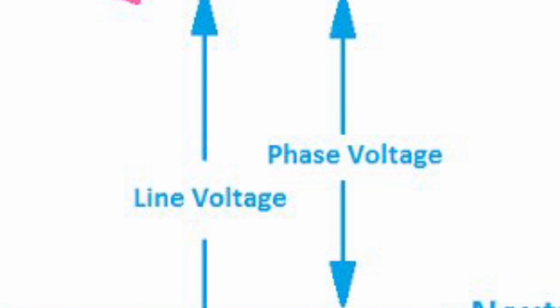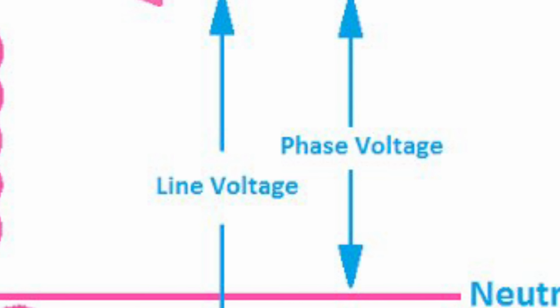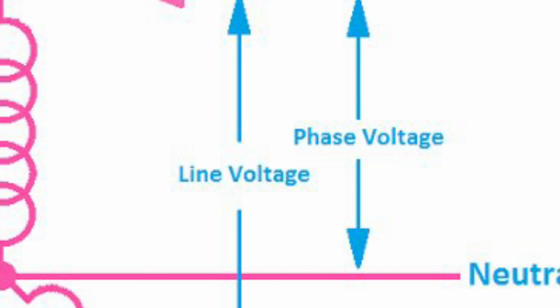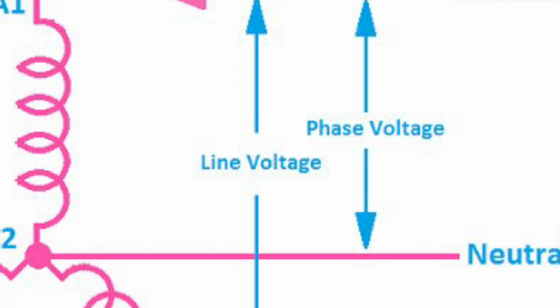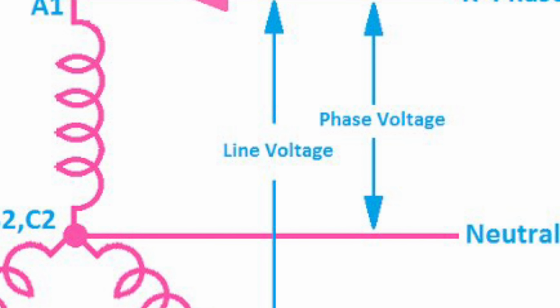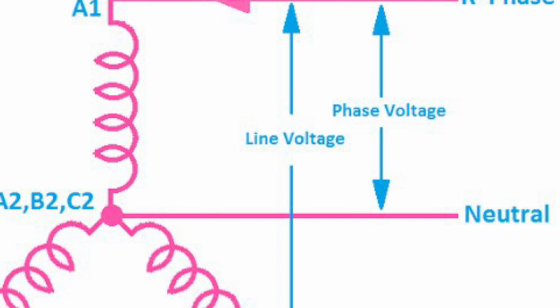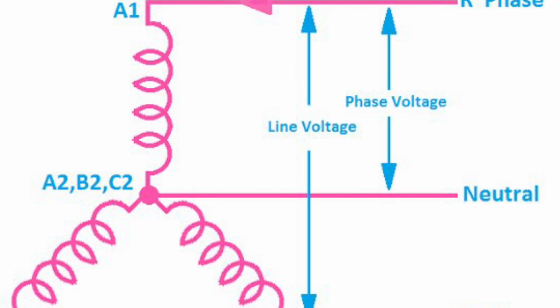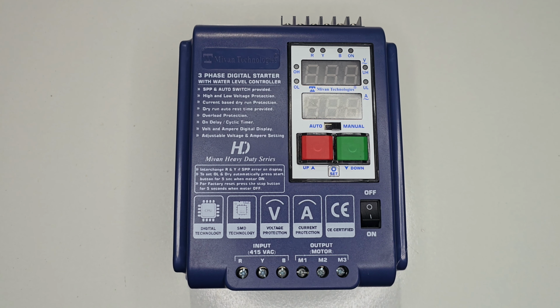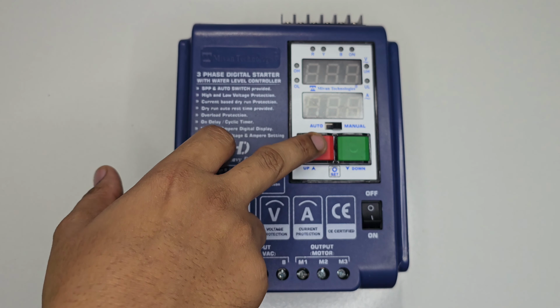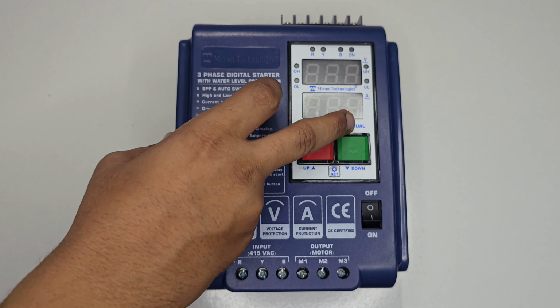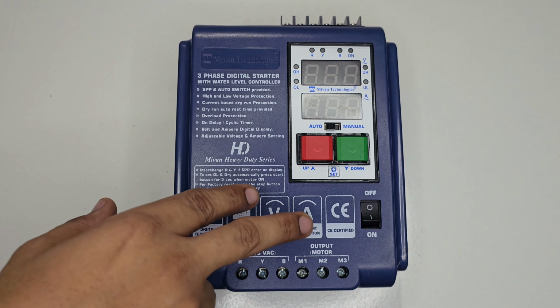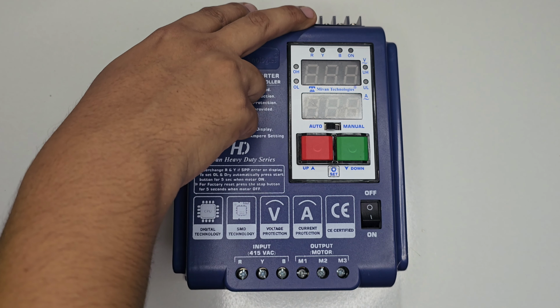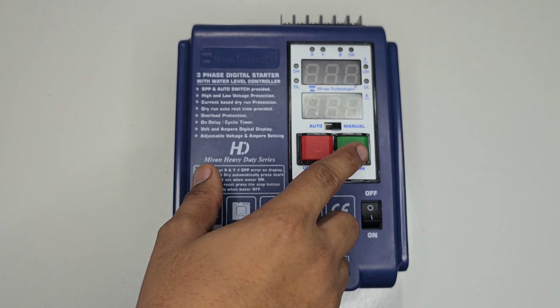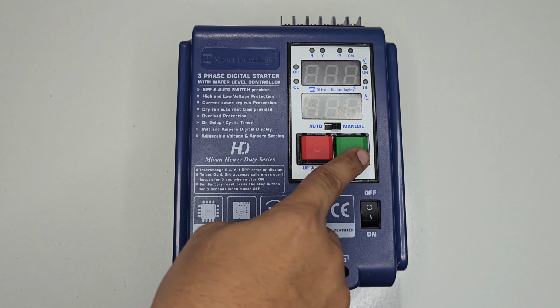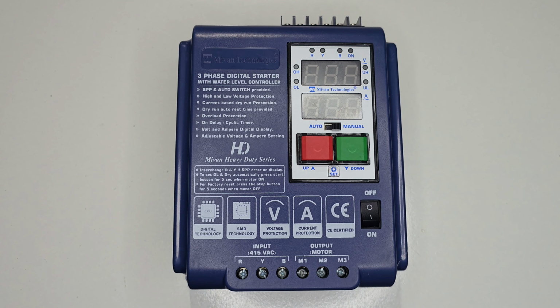This device also protects the motor from voltage unbalancing. If there is a voltage difference of more than 50 volts between any two phases, then this device will trip the motor. In this device, an auto and manual mode switch is available. In auto mode, the motor will start based on the water level in the tank. In manual mode, the user can start and stop the motor by pressing the start and stop button of the controller.